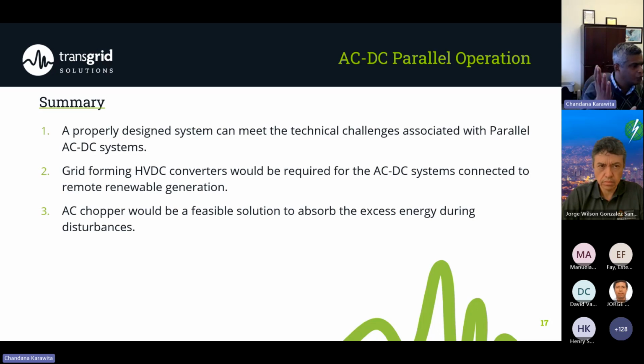But if you have crossing points where the AC and DC cross together, or if you have low voltage AC underneath DC, then the possibility of having AC to DC faults would be high. So you have to evaluate your application and find out whether this is a feasible issue. And if it is, you have to find out the impact of that.